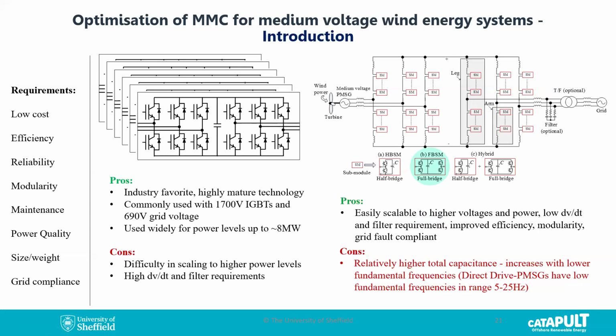And then the next topology would be a hybrid topology, where some modules are half bridges and some modules are full bridges. Each submodule has that capacitor, a flying capacitor, and that flying capacitor basically is the problem, because in MMC it sees the fundamental frequency. From the wind side, generator side, it can see as low a frequency as 5 hertz. And that frequency defines the size of the capacitor.